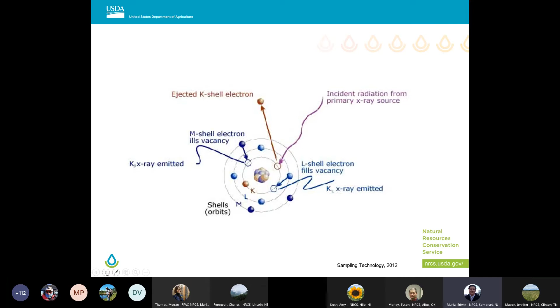So as I mentioned before, these are all the elements that the machine can pick up depending on the calibration and the model. So you can see it looks for a lot. So the potential of using this is incredible. And the reason that we use this model is because these limits of detection are within the ranges for the cleanup standards for the state of New Jersey.